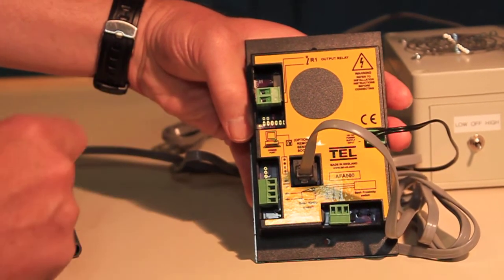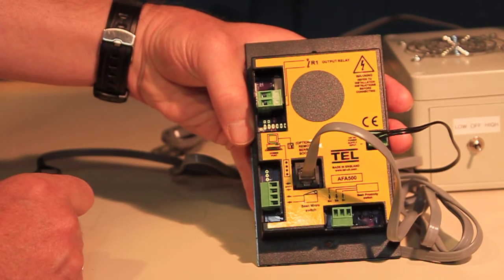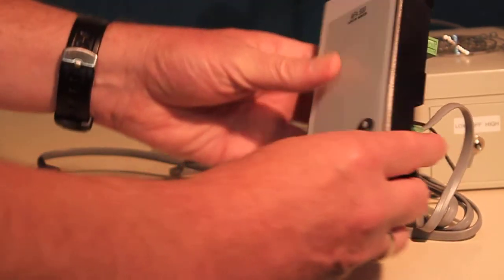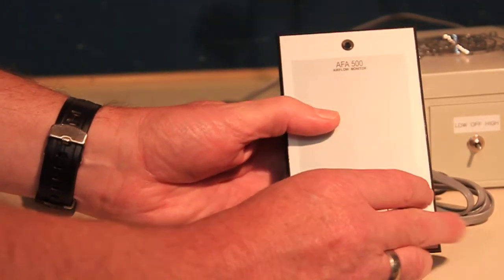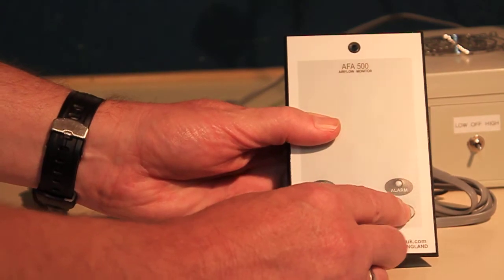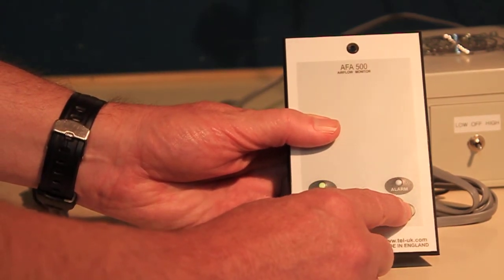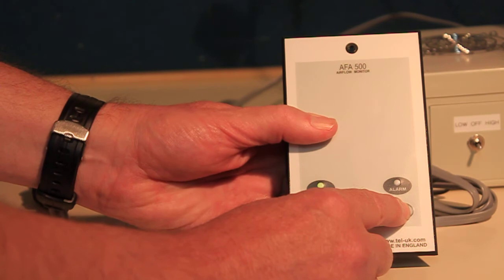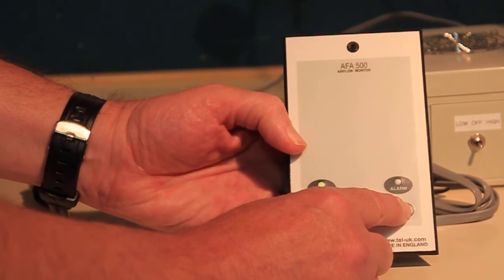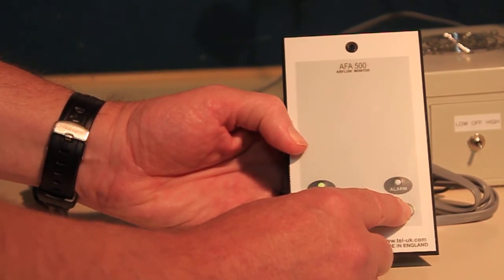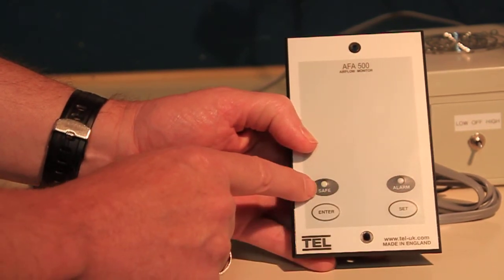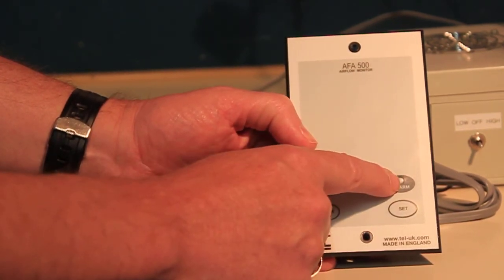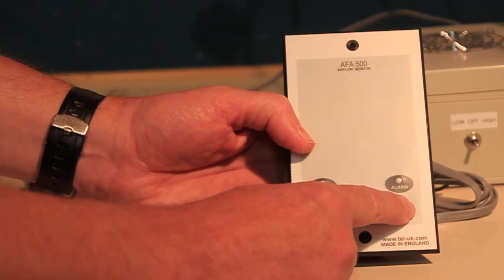In the event of an air fail alarm, pressing the Enter button once will silence the horn until the sensor sees enough airflow to return to safe mode. To permanently silence the alarm, press and hold the Set button for 10 seconds. In normal mode, with the alarm muted, the unit's green safe light will blink. When there's an air fail condition, the red alarm light will flash. To restore the audible alarm, press and hold the Set button again.